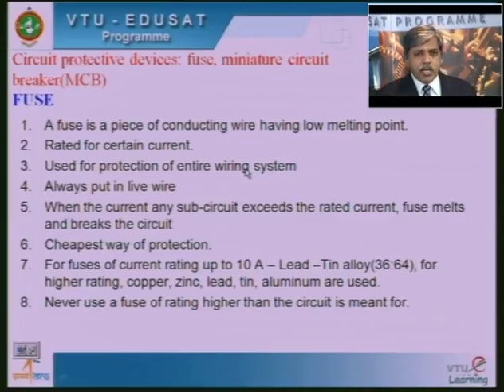What happens if the current drawn by the circuit exceeds the limit? Let us say I have an energy meter in my house which is rated for 5 amperes. That means if the total current drawn by the lighting system and all the power consuming equipment in the house put together is less than 5 amperes, the fuse will be intact. If I switch on all the loads, all lamps, all fans, all geysers, all refrigerators at a single time, then my current is, let us say, 7 amperes. I put a fuse of 5 amperes. So 7 is much larger than 5.